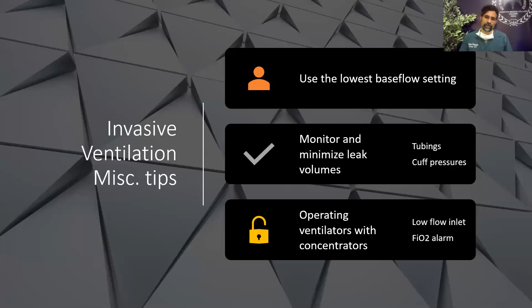The other consideration is if you have a large oxygen concentrator, you must remember that it is not going to provide 99% pure oxygen. Because of the lower percentage of oxygen in the oxygen supply, you will start getting constant low FiO2 alarms on the ventilator. So if you're going to be switching over your ventilators to a large concentrator source, you must have the ability to switch off these FiO2 alarms.